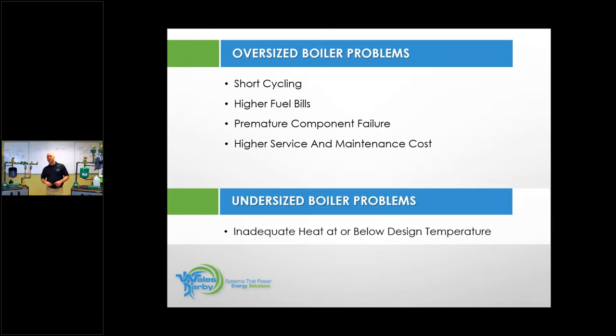Oversizing of a boiler, what are the problems? Short cycling, higher fuel bills, premature control failures, and higher service and maintenance costs. So in short, if I oversize it and it stops and starts, that's like taking your service van down the busiest road you know with a red light every other block and getting every red light. Stop and go, stop and go, stop and go. You use a lot more fuel.